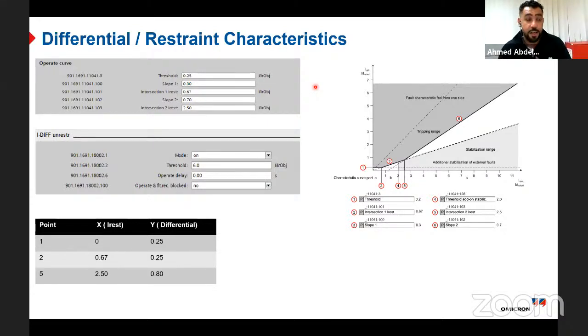And as I said, in Omicron we have something we call the Protection Testing Library, PTL, which helps you a lot to understand the function and saves your time while you're testing. At the end, you will calculate 3 points, point number 1, point number 2 and point number 5. This is what you need to calculate if you would like to draw the characteristic of the relay manually.